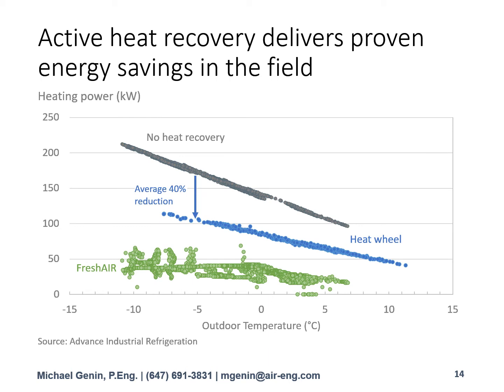I've rarely seen heat wheels operate anywhere near the 80% that they claim, but this was certainly an older model heat wheel. And then in the green, you have fresh air active heat recovery, which is by far lower and delivered in this case example an average reduction of 78%.